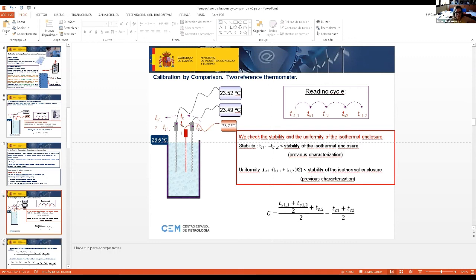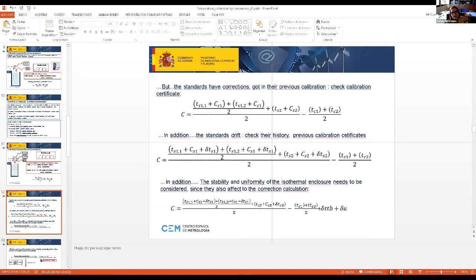Okay, so this is the beginning. Why? Because I told you that the standards have been previously calibrated, so they have corrections that they got in the previous calibration certificates. Check the calibration certificate to include the corrections of our standards. In addition, as Andrea told you previously, the standards, or all the instruments, drift. We need to check the history of our standards, and then we need to include this drift in our mathematical model.